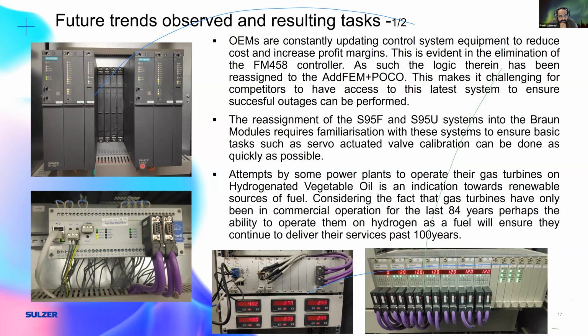In the past, there was a module here called the FM458, and this has now been taken out. It means this module is no longer required. It cuts the costs, and the profit margins grow. What did they do with the functions that are processed here? They outsourced them into the AddFEM module. So the AddFEM module is a module that takes in very fast signals like speed and valve positions, and they've incorporated some microcontrollers there as well, with the ability to perform certain tasks in order to relieve the automation processor.